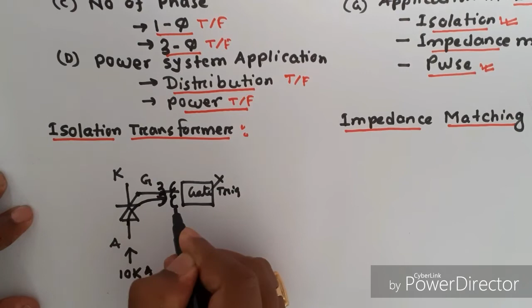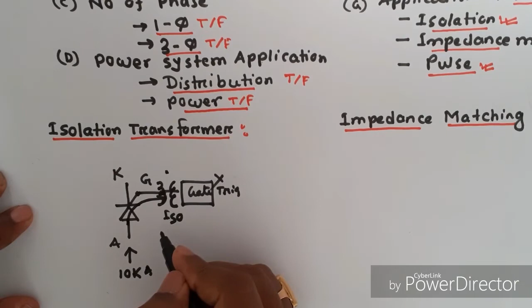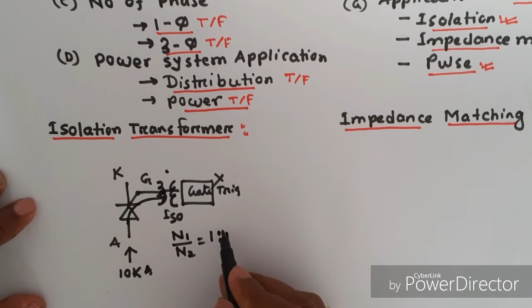If this SCR gets damaged, then this isolation transformer will be damaged, but it will not damage the gate triggering circuit. That means, for the purpose of protection, we use an isolation transformer. The isolation transformer turns ratio N1 by N2 is 1:1. It does not increase or decrease the voltage - input voltage equals output voltage. Here the purpose is to protect the low power circuit from the high power circuit.